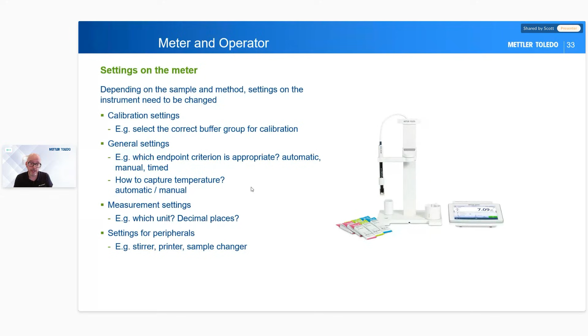Which general settings? What's the endpoint criteria? How do we capture the temperature? Measurement settings, so which unit, how many decimal places are we measuring? Then we've got peripherals like stirrers, printers, sample changers, lots of different things there with the pH system that we need to look at and make sure the settings are correct for when we start using the pH meter. So we've got our meter, we know we set it up right. We'll make sure that everything's turned on correctly and everything's sorted.